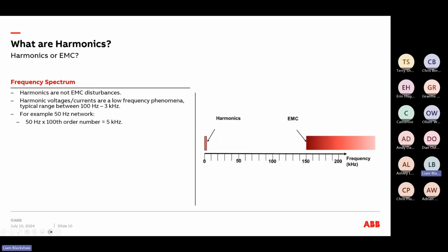Harmonics and EMC are quite an interesting aspect, and a key thing to say is that harmonics are not EMC disturbances. Harmonic voltages and currents are a low frequency phenomenon, typically ranging between 100 hertz and 3 kilohertz. Harmonics do not mean the same thing as radio frequency interference, where that spectrum is wide, covering a whole range of frequencies. Some of those frequencies are in the realm of harmonics, whereas others fall under the EMC directive. They are not the same and have different solutions, where harmonics is typically a low frequency relation to the supply side, and EMC is more to the high frequency side, typically above 100 kilohertz, roughly, at least anyway.